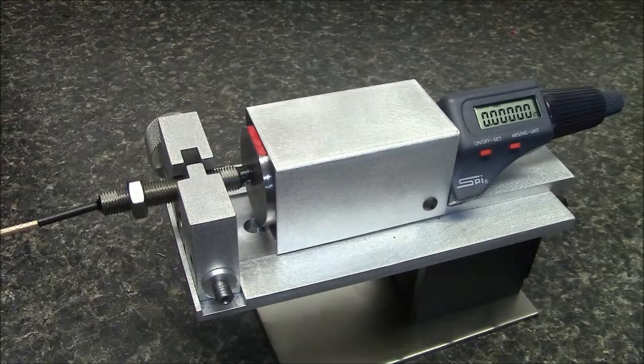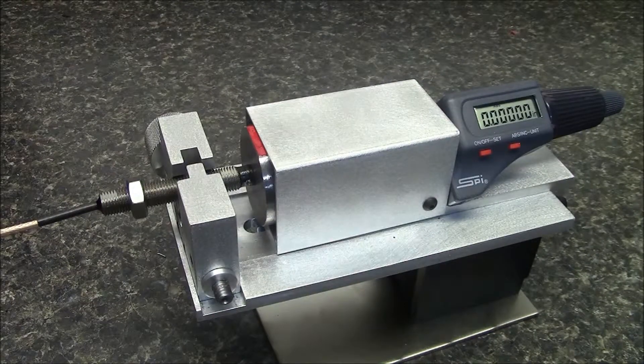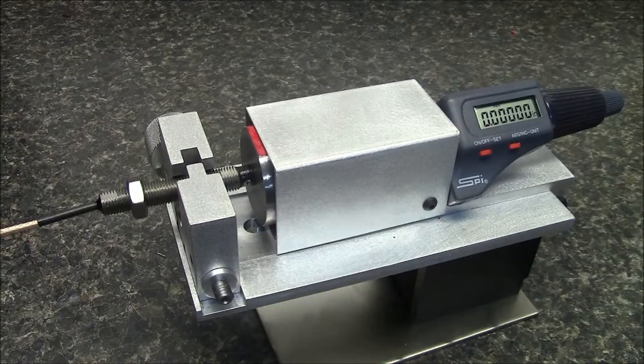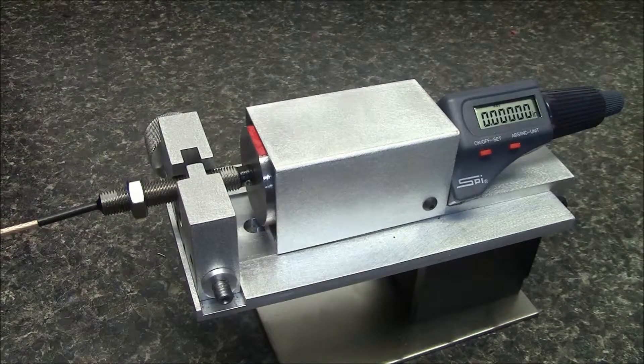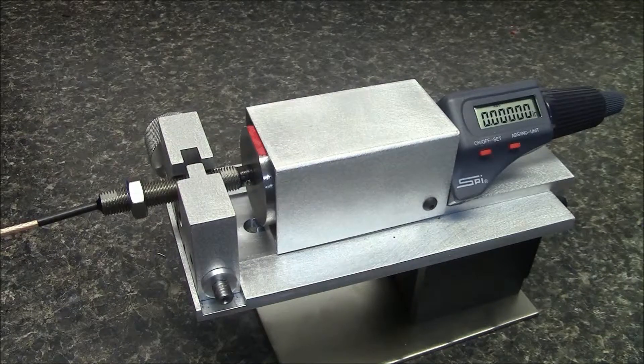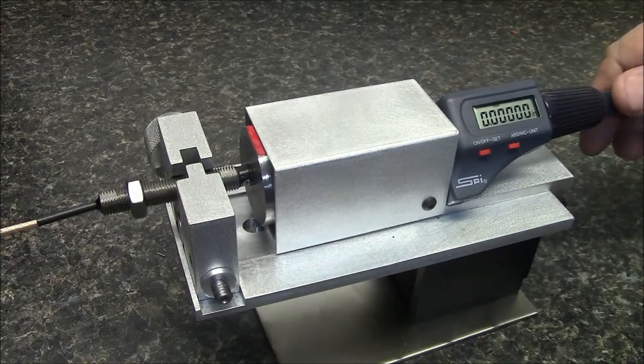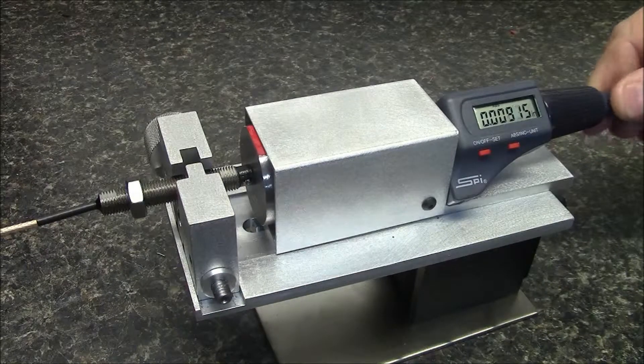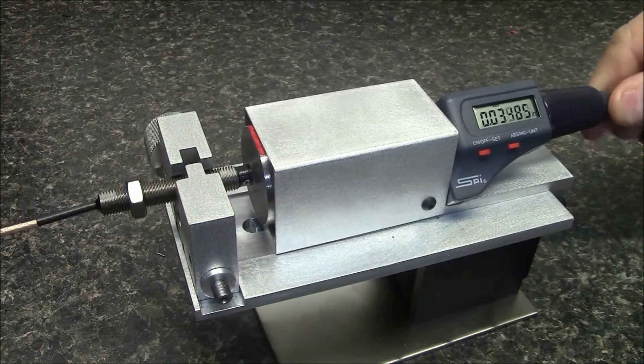Electrical run-out is caused by internal variations in the alloy mix of the target material and they only affect the probe reading if that alloy variation changes due to the rotation of the target material. Therefore, we eliminate the possibility of electrical run-out by using a non-rotating target material.